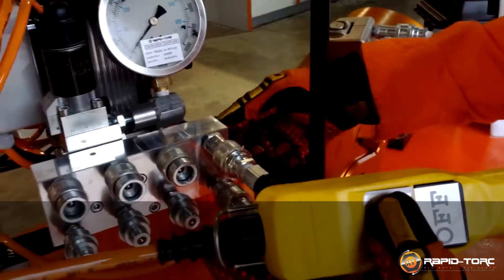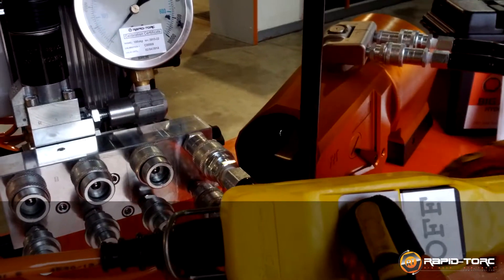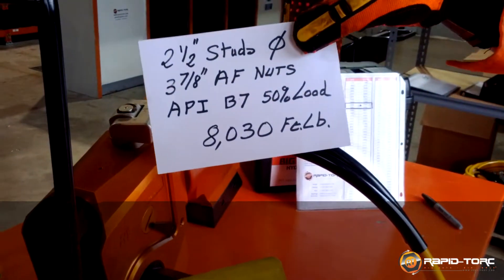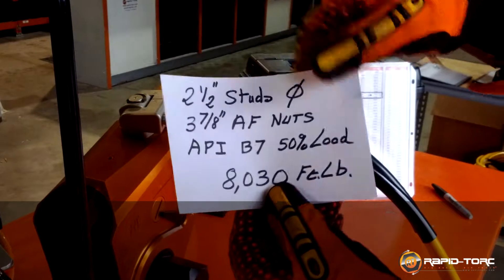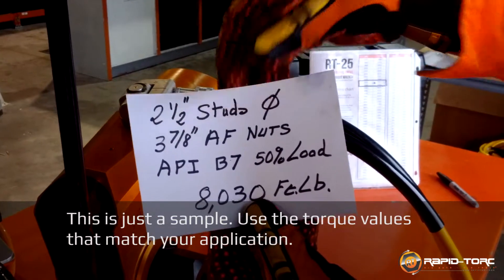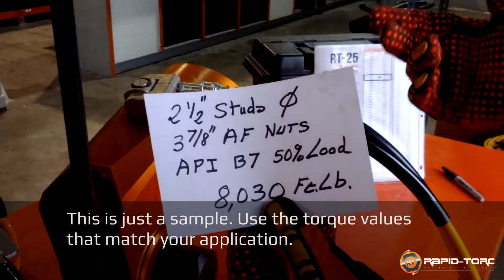Make sure that the pressure valve is not fully tight, just a little bit. Now, let's say we are going to go for 8030 foot-pounds — for example, a two and a half inch stud diameter, 3 7/8 inch across flat. This is a torque of 8030 foot-pounds.